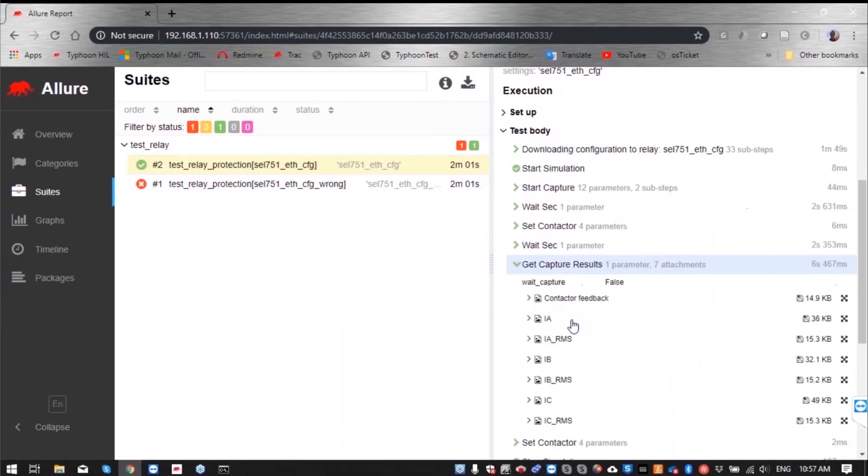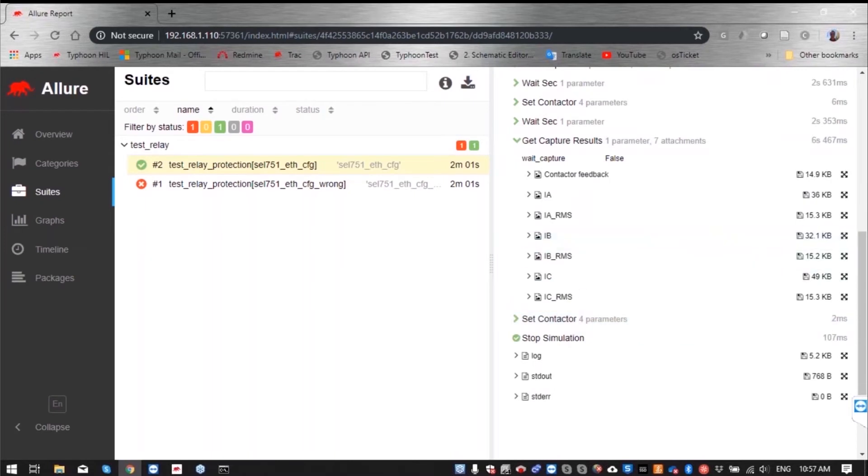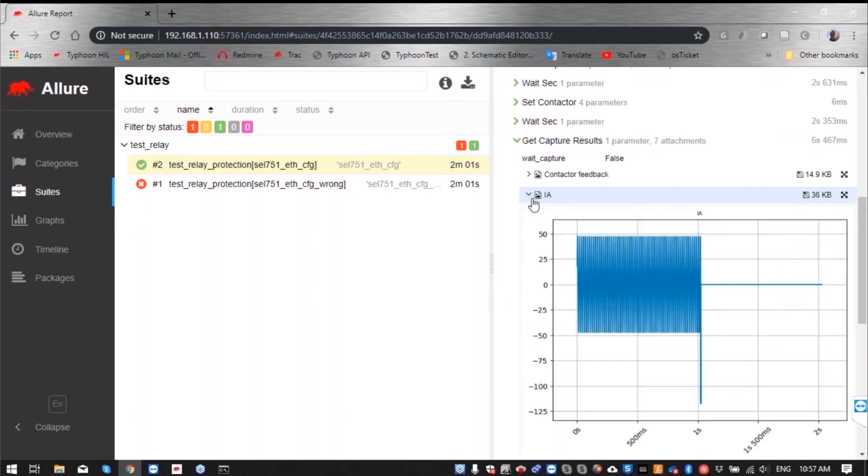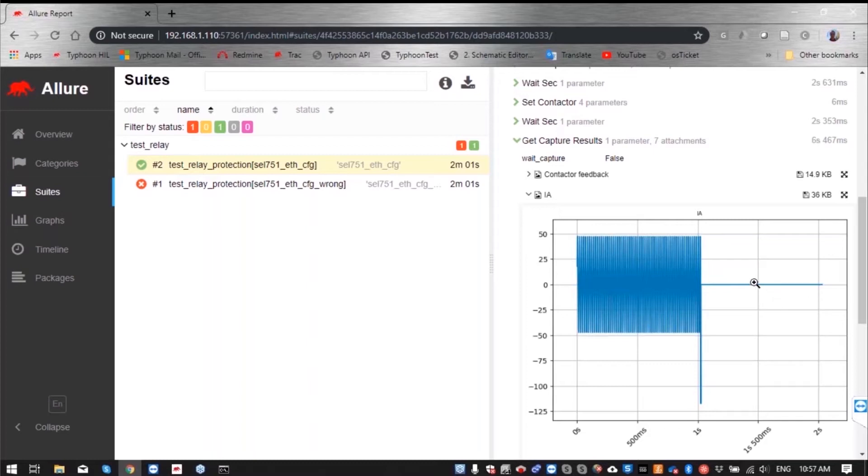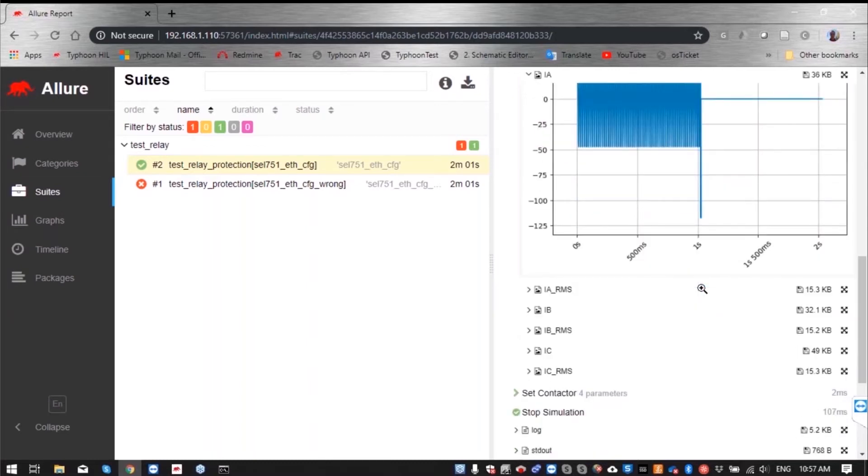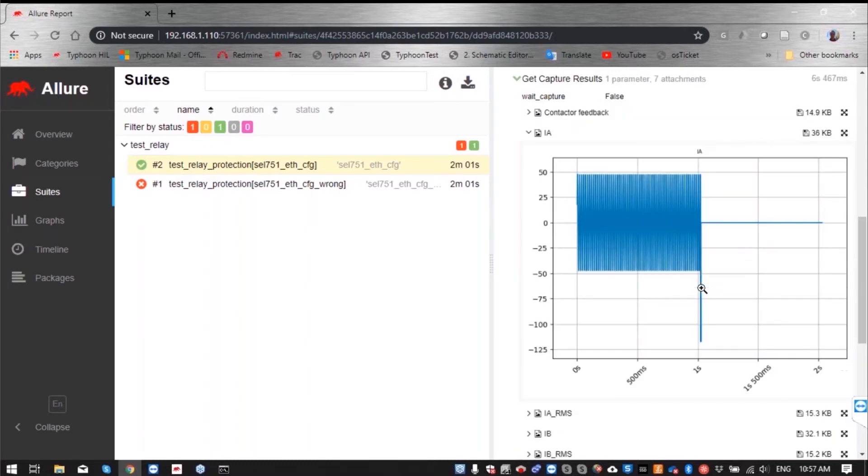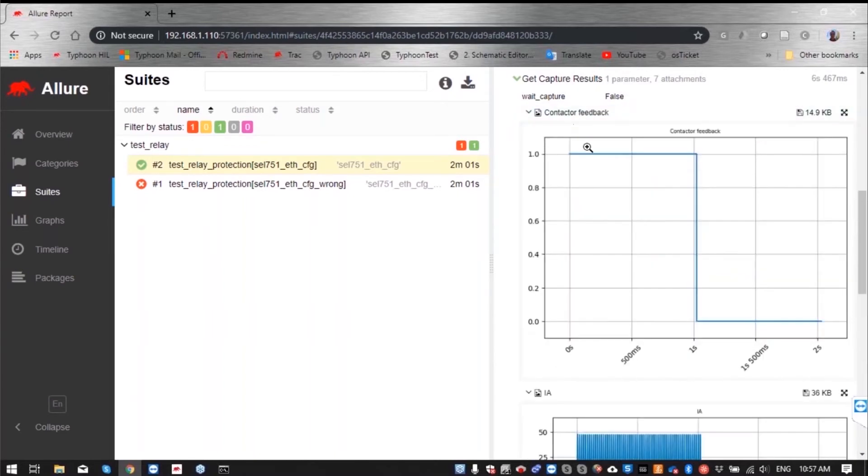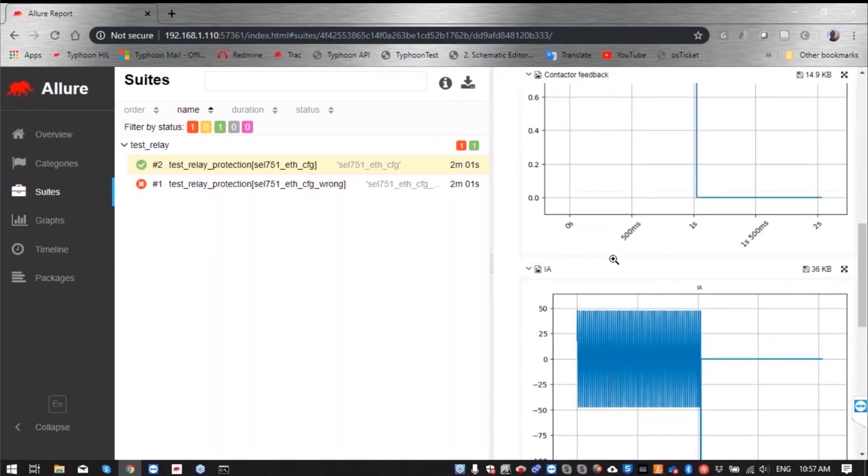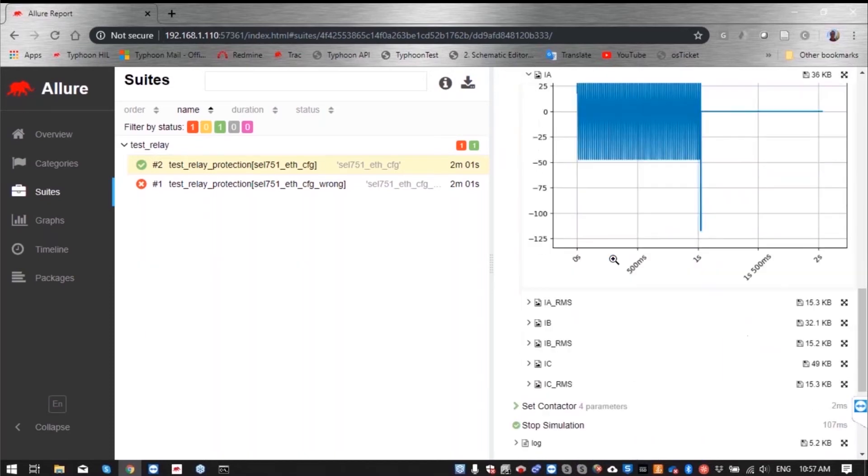We can see that it went really high and then goes back down to zero, that means that probably our relay acted and opened the contactor to protect that line and stop feeding the short circuit. We can basically confirm this by the contactor feedback signal and we can see that contactor went down to zero, meaning that contactor is open. And that's why this test is passed.